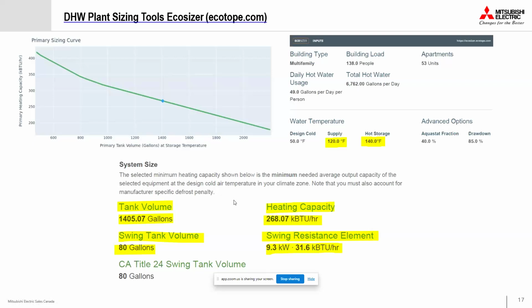Generally, if you go on the side, you will see that you can provide the input of the building load, like how many people or the occupancy, number of apartments, and what criteria you want to use. In this case, I use 49 gallons per day, but as per your design, you can use either HRAI low or the City of Vancouver guideline, or actual use if you have an existing building. That will change your total gallons per day and the capacity as per the design. Generally, our storage is 140 degrees Fahrenheit, just to avoid the Legionella problem, and 120 degrees supply. This is all standard in most designs in all cities or municipalities. So with all that information, you will get the heating capacity requirements.